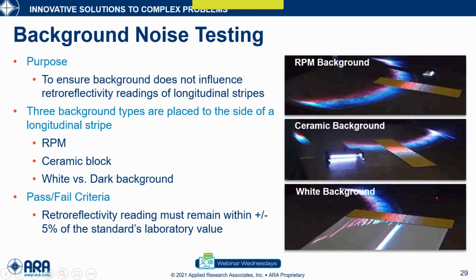At the end of the day, the criterion is that the readings measured with the interferences, with the 3 different backgrounds, should be within 5% of the standard laboratory value of this longitudinal stripe without any of these interferences.